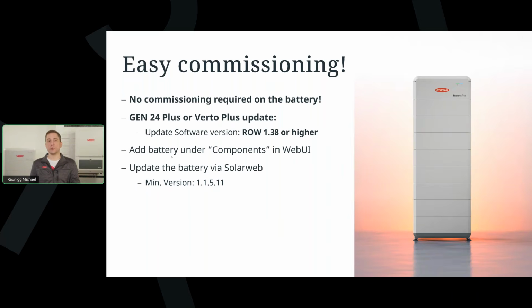Please note, after the installation process, make sure to watch the online SolarWeb system, and make sure that the newest firmware version of the battery system is installed. For the operation of the system, you need a minimum battery firmware version of 1.1.5.11. So please watch this directly in SolarWeb. And whenever a firmware update is needed for the battery, this is done directly online via SolarWeb. So there is also no need to go to the customer site. You can make this easily from your office. For example, you just log into the SolarWeb system of the customer, check the components page in SolarWeb, and then you can easily do the firmware update of the battery system from afar.